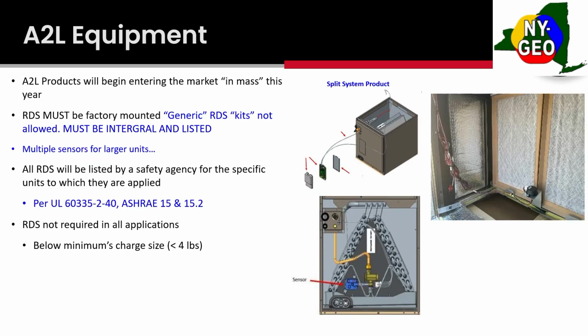So here's what the A2L equipment looks like. Has anybody used A2L equipment yet? Show of hands. Okay. So here's a return air of a rooftop unit. On a rooftop unit, you're going to have an RDS in your return air. Depending on the size of it, you might have two. Here's a coil from a split system. It's going to be mounted on the outside with your sensor on the inside.